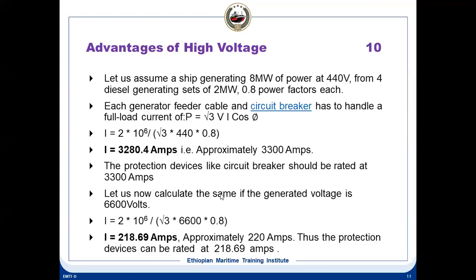Power is roughly VI cos phi, and in the case of three-phase AC power it is √3 into VI cos phi. So if you take out the current from this, you get 2 into 10 raised to 6, because it is a 2 megawatt generator, divided by √3 into 440 into 0.8. That means the current flowing in this case will be approximately 3280.4 amps, about 3300 amps. So protection devices like a breaker should be rated at 3300 amps. The rating of the breaker should be very high.